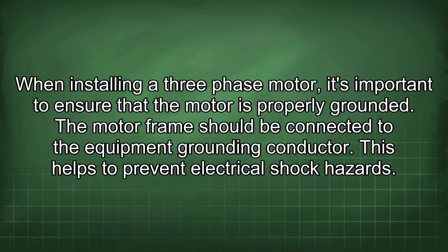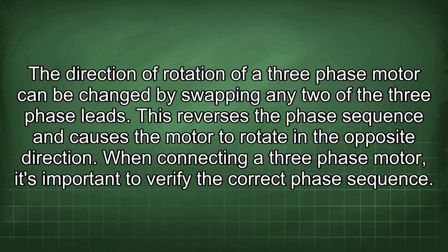When installing a three-phase motor, it's important to ensure that the motor is properly grounded. The motor frame should be connected to the equipment grounding conductor. This helps to prevent electrical shock hazards. The direction of rotation of a three-phase motor can be changed by swapping any two of the three-phase leads. This reverses the phase sequence and causes the motor to rotate in the opposite direction.